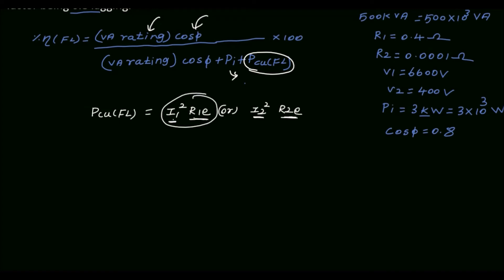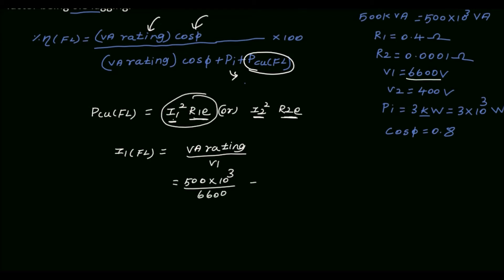The VA rating is the product of voltage and current, so we can find the primary full load current I1. The full load primary current I1 equals VA rating divided by V1, which is 500 × 10³ divided by 6600 volt. So I1 is 75.7575 amps.